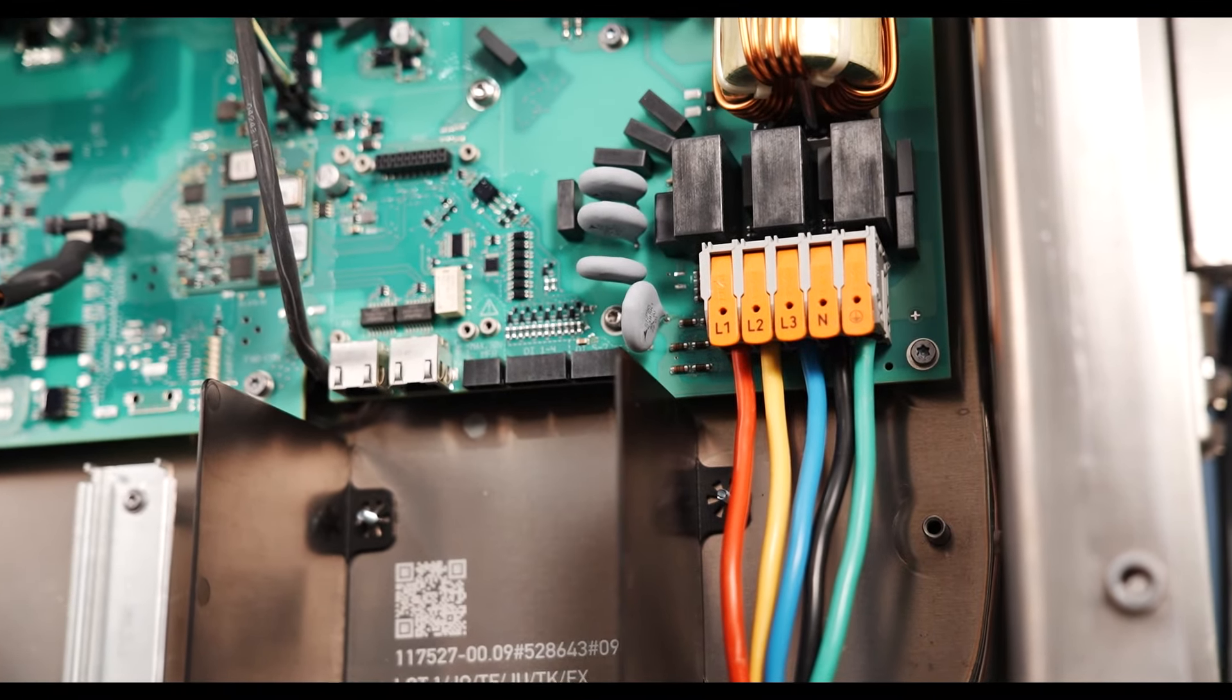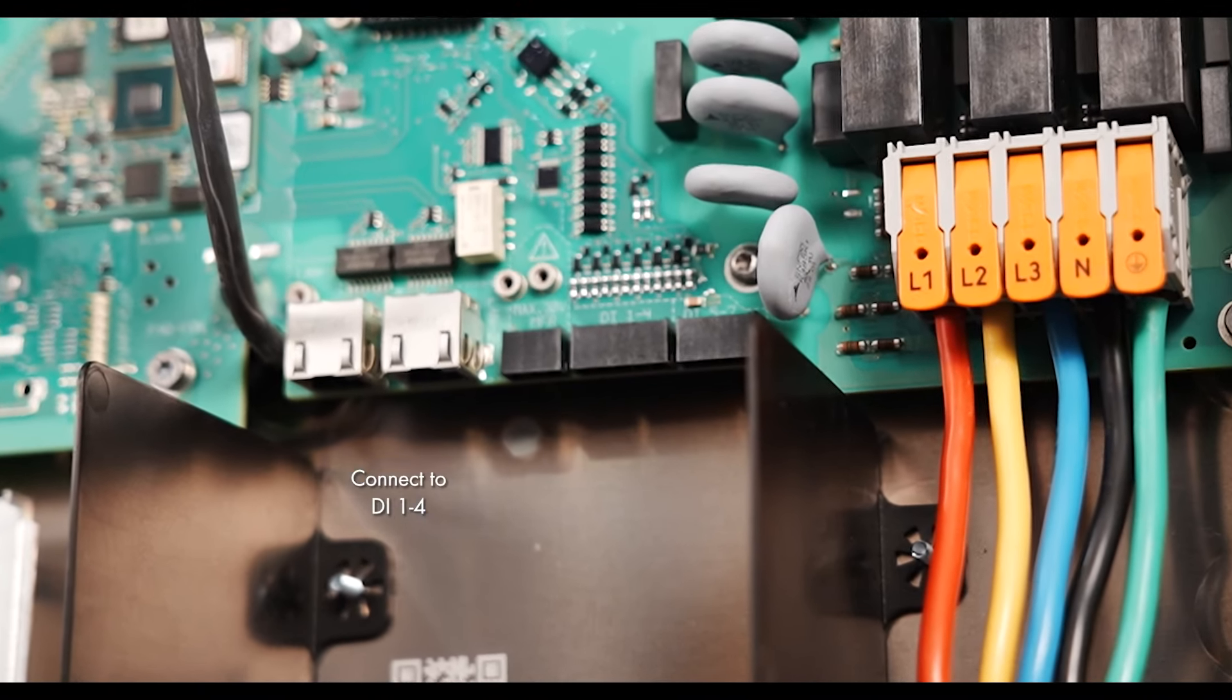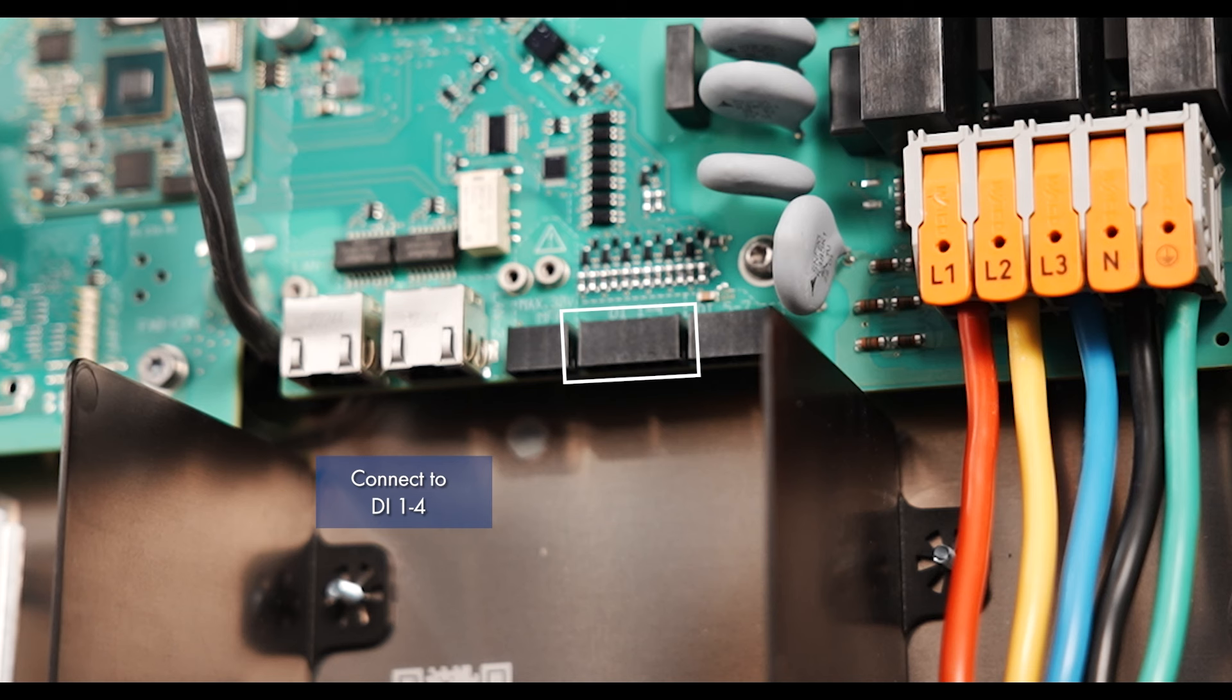A ripple control receiver or remote terminal unit can be connected to digital input DI 1-4. In a multi-inverter system, the ripple control receiver must be connected to digital input DI 1-4 of the system manager. You can connect a fast stop switch at digital input 5 and an external grid and PV system protection device at digital input 6.